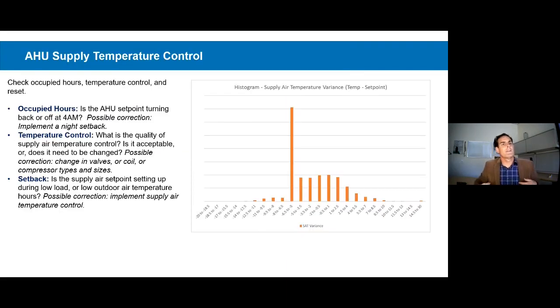Another diagnostic that designers should always be interested in is the variance around any controlled point, a controlled temperature or a controlled pressure. We could look at this for any controlled point: supply air temperature, pressure, water temperature, etc. In this case, we're looking at air handler supply air temperature control. And just to let you know, the ranges that we find are often not normally distributed, like this one is not a normal distribution, and they're also not symmetrical, and they're not centered on the center point that we would expect them to be centered on.